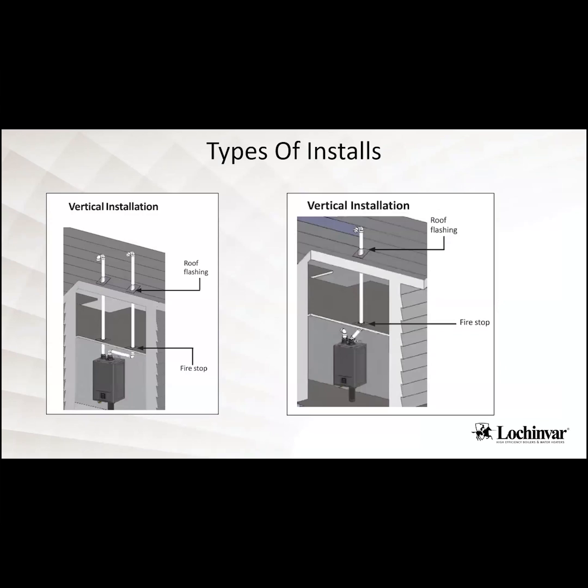You mean like this right here? Yeah, on the exhaust, they're showing that gooseneck, and that's not really standard practice. With most condensing appliances, you want that going straight out, and then you gooseneck your intake. With these, they want you to 45 off that exhaust, and if you're going to intake through that roof, they want you to 90 it off. So you're finishing with a 45 coming out like that. The reason is to block any direct wind coming in, and especially going out the roof, it protects it from rain and snow coming straight down it.